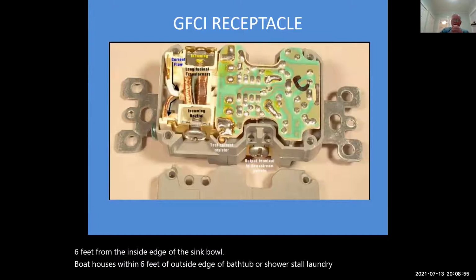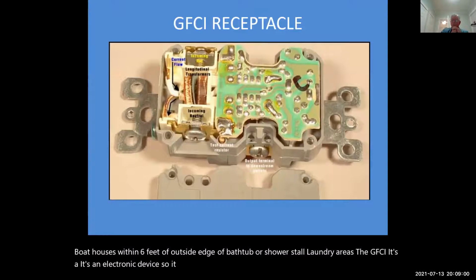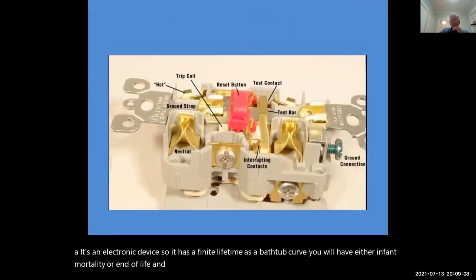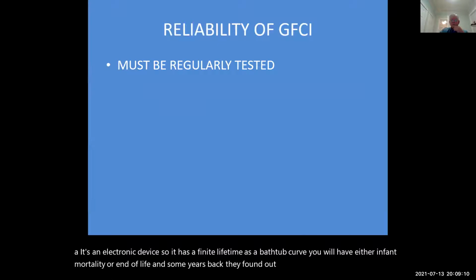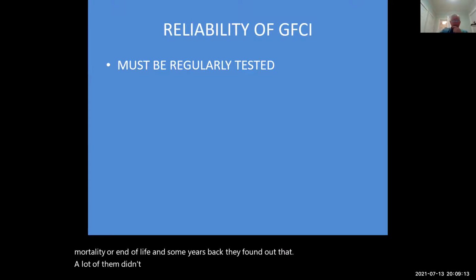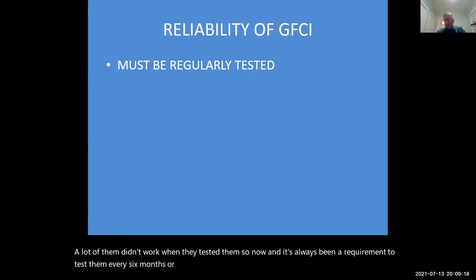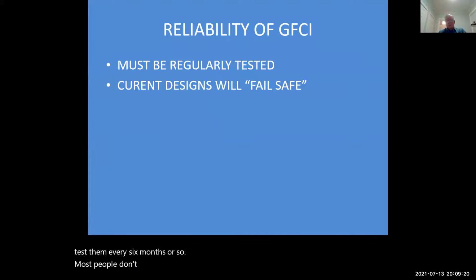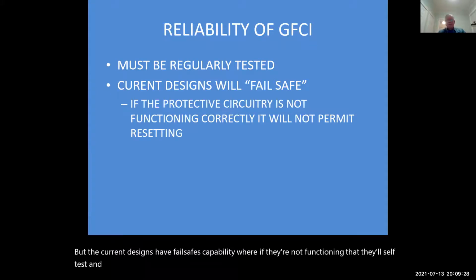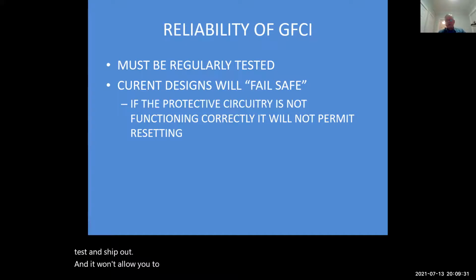The GFCI is an electronic device, so it has a finite lifetime, it has a bathtub curve. You will have either infant mortality or end of life. And some years back, they found out that a lot of them didn't work when they tested them. So now, and it's always been a requirement to test them every 6 months or so, most people don't, but the current designs have fail-safe capability where if they're not functioning, they'll self-test and trip out, and it won't allow you to reset it until you replace it.